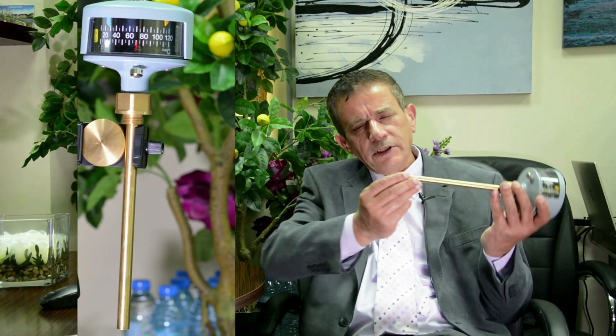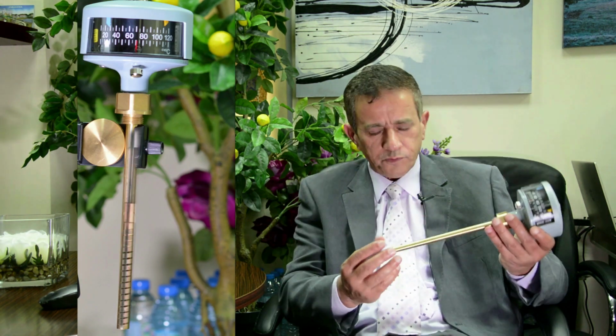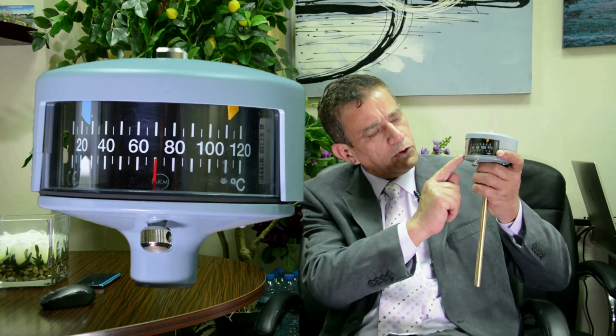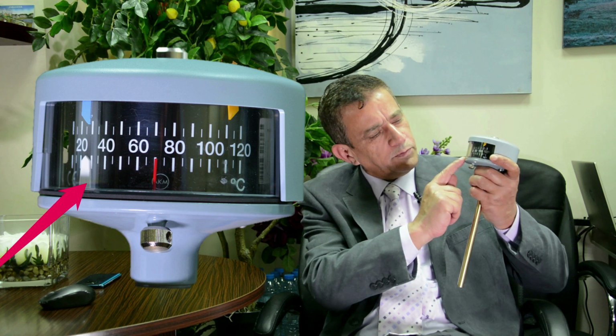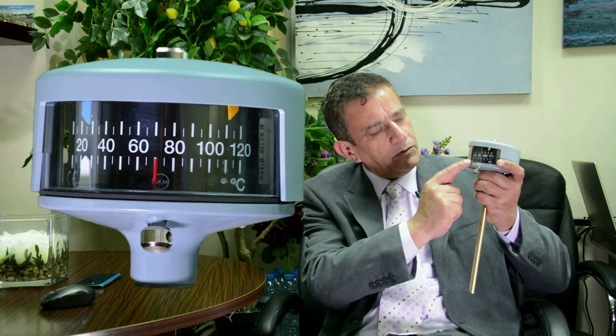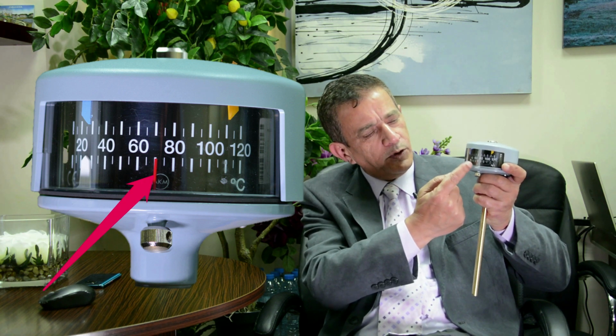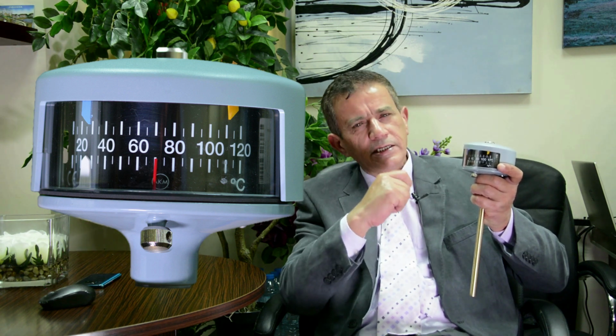Normally the two materials are either copper and steel or brass and steel, and the helical or spiral shape is formed inside this tube, and this will be inside the oil of the transformer. If we heat it, this heat will be converted into mechanical movement, which will move this pointer, the white pointer, and we can see here there is a red one. The red pointer will record the maximum temperature, and sometimes this can come without contact, sometimes with contacts.